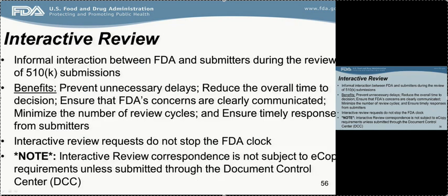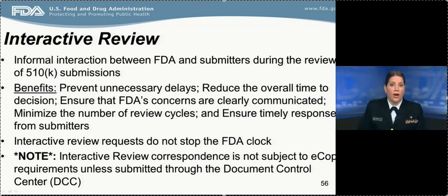Interactive review is an informal interaction between FDA and the submitters during the review of your 510K. Interactive review requests do not stop the FDA clock. That can be very beneficial because it prevents unnecessary delays, it may reduce the overall time to decision, and it ensures that timely responses from submitters are received. The reviewer will determine whether or not interactive review is appropriate. Please note, though, that interactive review correspondence is not subject to e-copy requirements unless you submit information that is needed for the interactive review through the Document Control Center. So anything that is submitted to the Document Control Center must have a valid e-copy.